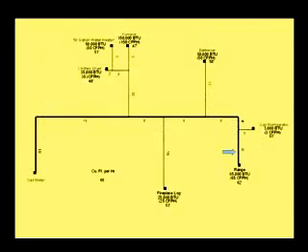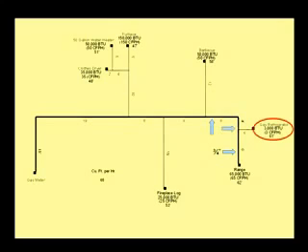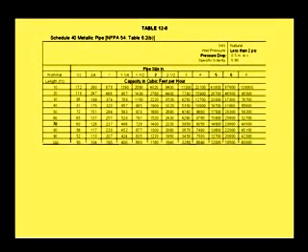Working backwards, the next section of pipe will be supplying the gas refrigerator, which has a demand of 3 cubic feet per hour, plus the 65 cubic feet per hour from the range, for a total demand of 68 cubic feet per hour. Refer to table 12-8, 70-foot row — 68 fits under 126 — and see that a 3/4-inch pipe will accommodate both the 4-foot and 6-foot sections.